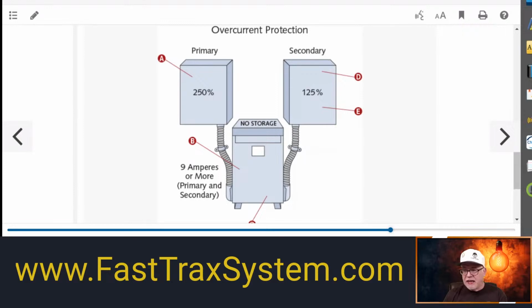Then they go to the secondary, and they do the same thing, but they size their panels and loads indicative of what the transformer can actually handle. And so if it is a 208 amp secondary, it means 208 amps are being pulled out of it. And let me make sure, excuse me, let's see, hold on real quick. 75,000 divided by, let's see here, 360. Just give me a rough number. Yeah, so if it's 208 amps, they might go to a 225. And then the conductors will be rated 225. But the most I know, a 75 will probably supply a 200 amp, okay? That type of thing. So just keep that in mind when you're doing transformers, that those are maximum numbers. You don't have to go to maximum, okay?